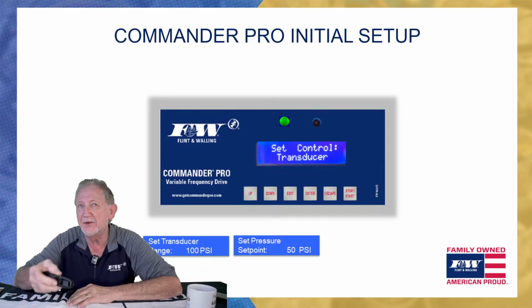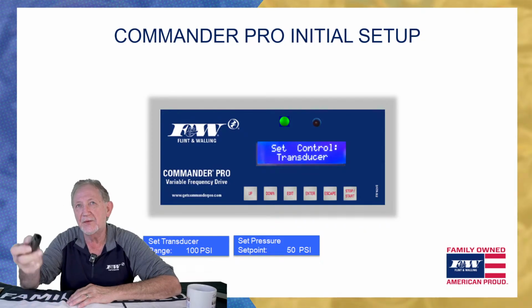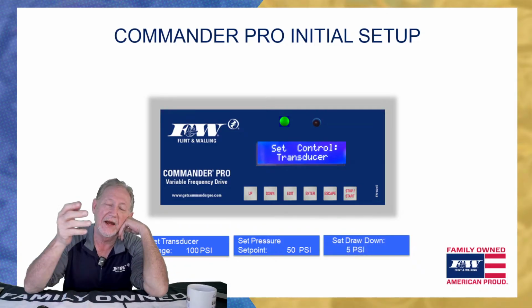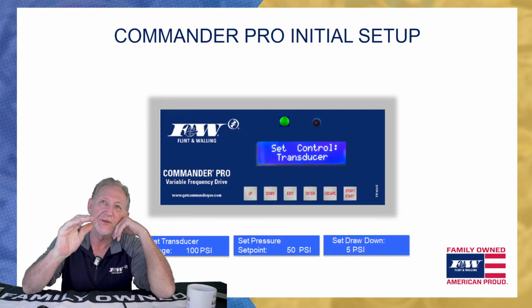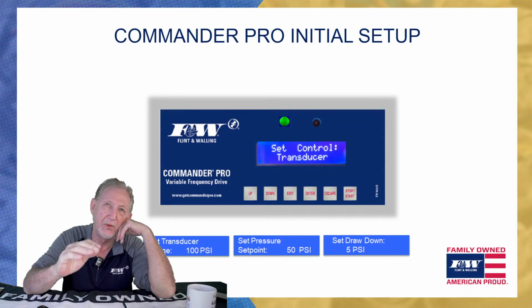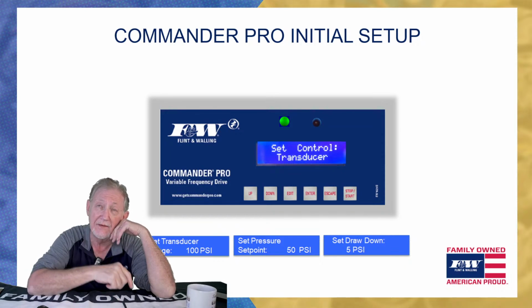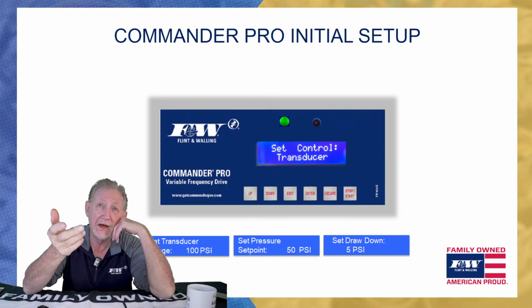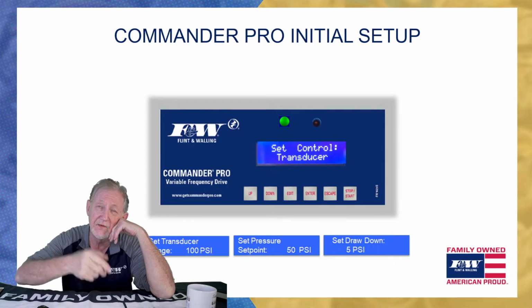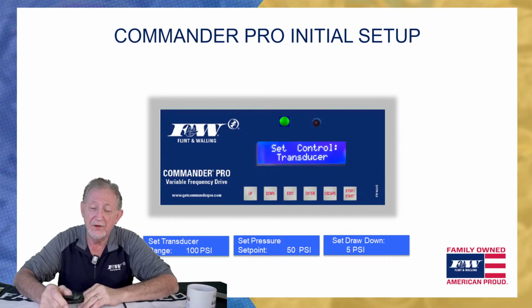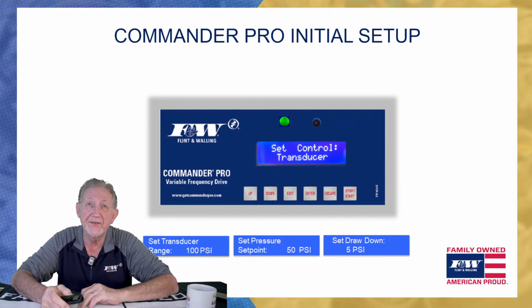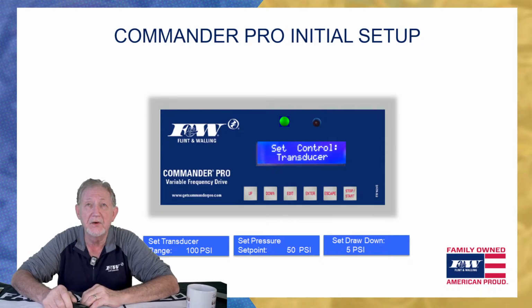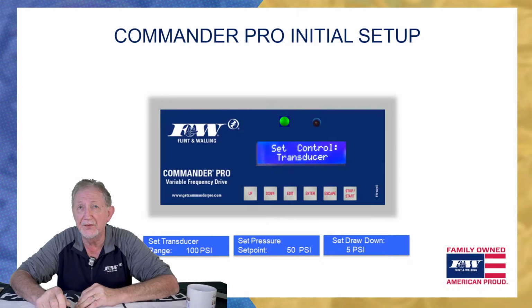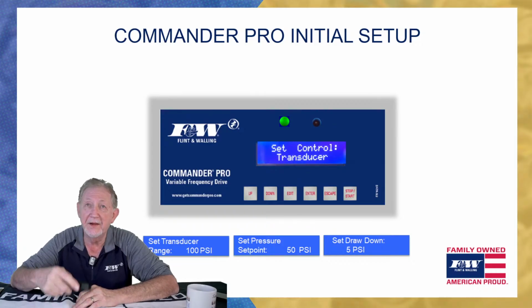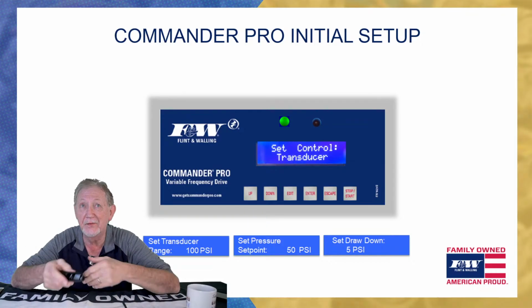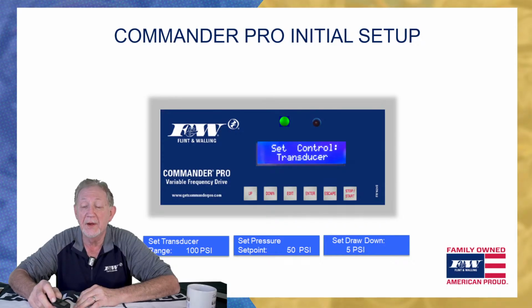And then the last of that three menus, and this is simple stuff here, the last of that three menus is what's simply called drawdown, all right? How far below that pressure set point, how many pounds below that pressure set point do you want that system to drop before that drive comes on? It's going to leave here at a factory default of 5 psi. So if you've got a 50 psi set point, that drive is going to kick on when that drawdown gets down to 45 psi. Now that is also adjustable, as are all these menus. They're fully adjustable. You hit the edit button, up and down, and hit the enter. It's that keystroke that's consistent throughout the programming of this drive.